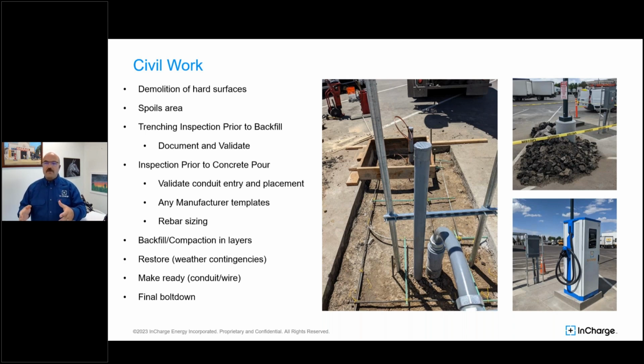This part is so critical because quite often somebody has the charger turned 90 degrees and now the cable won't reach the way it was designed. Or they planned on one type of charger and then the charger type changed, so now the conduit's in the wrong spot relative to the size of the base. This validation before you pour concrete is very critical because sometimes it gets moved a little bit one way or the other, and now you can't open a door on the charger, so you can't service it, can't start it up, and it creates a lot of friction unnecessarily at the end of the project.